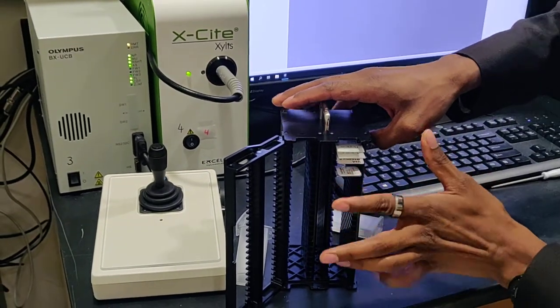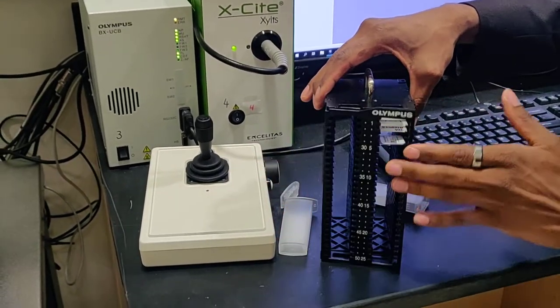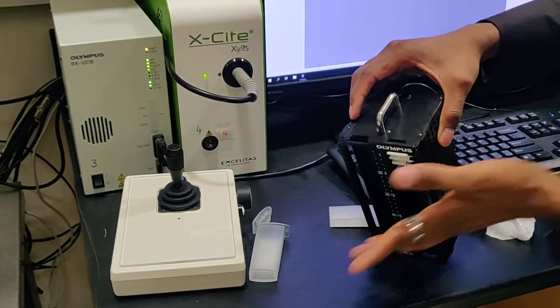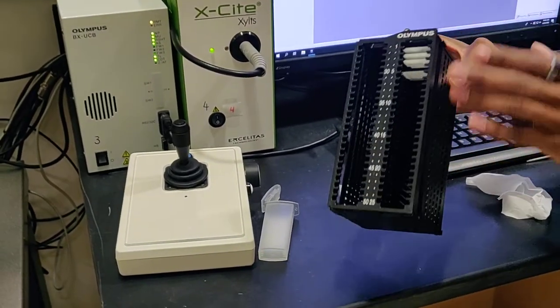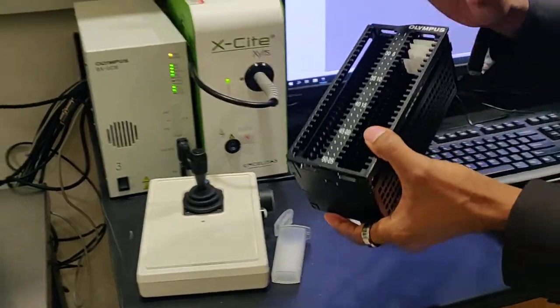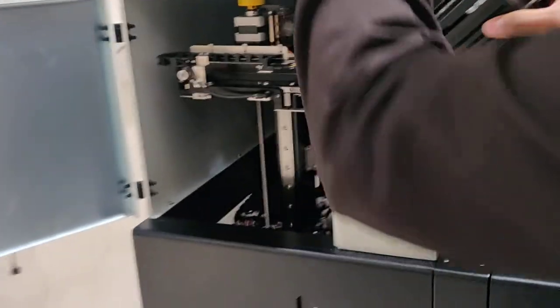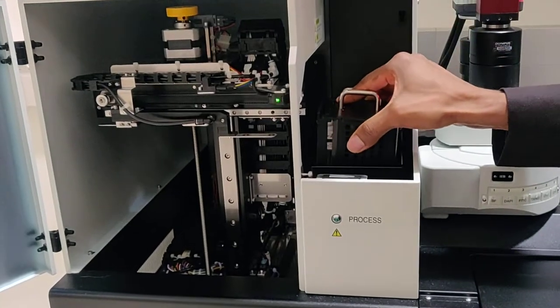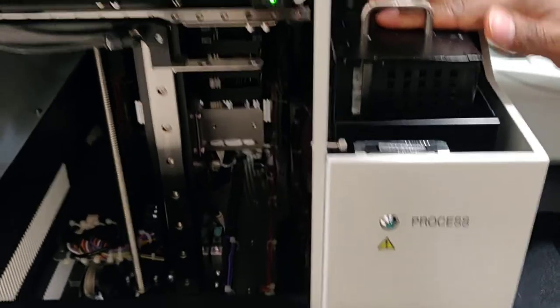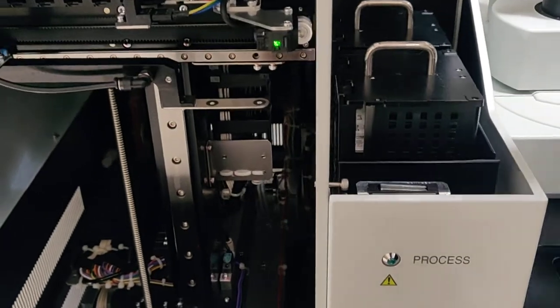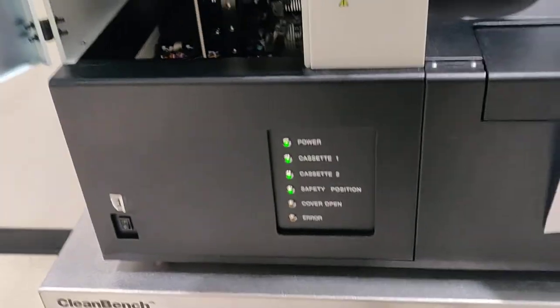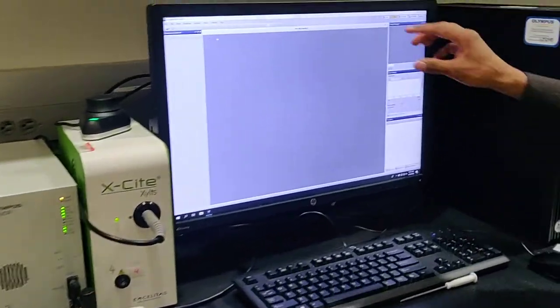I will place it in here. I kept a gap so I can identify where it is. And while loading, sometimes people push it like this and the slide pops out. Make sure it is not doing that. Lock it up a few times here like this. Everything is all set. All of them are green. I close the cover. Everything is fine.